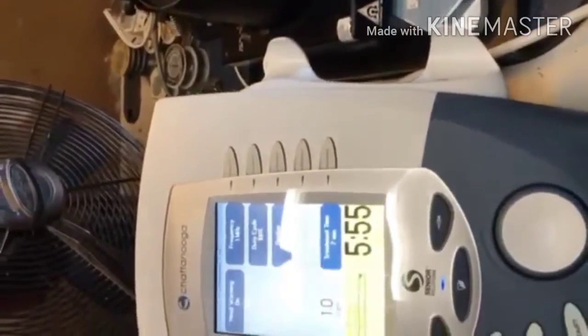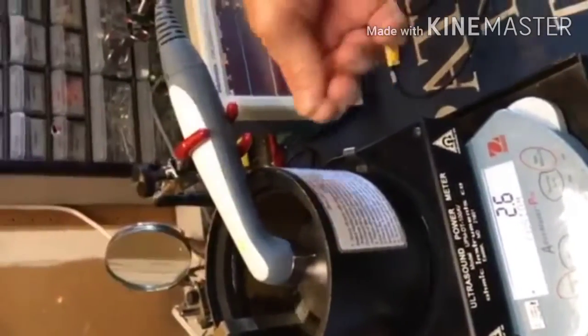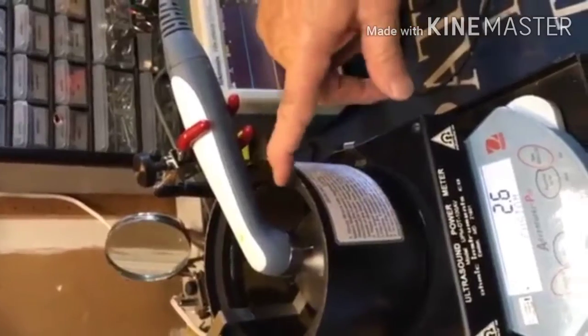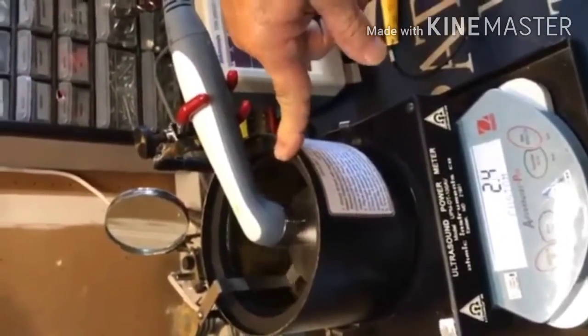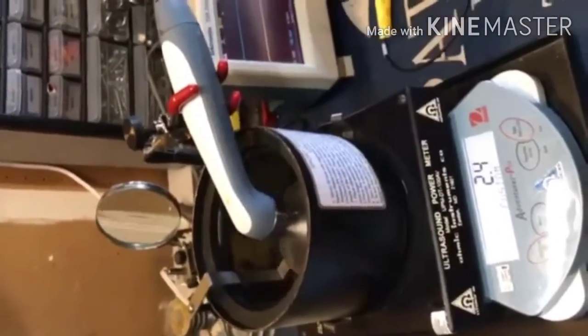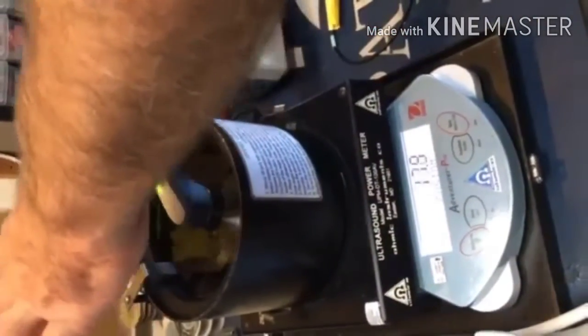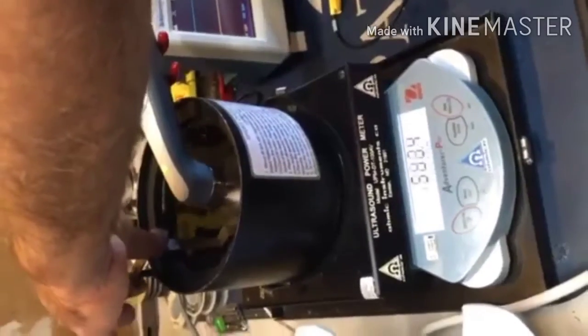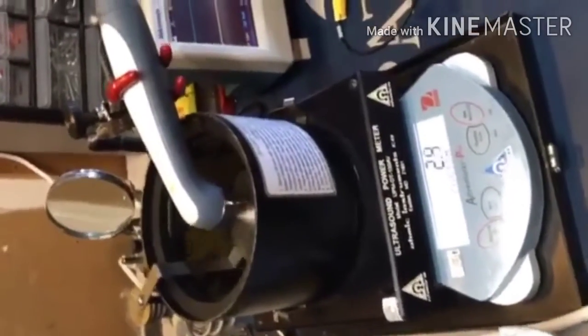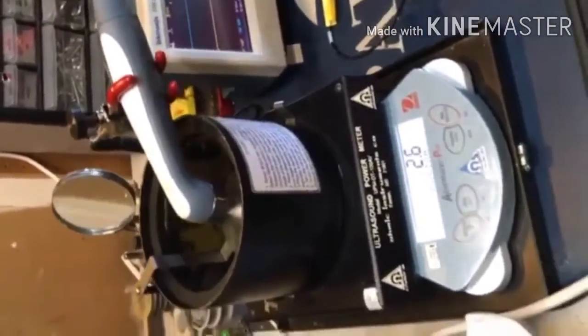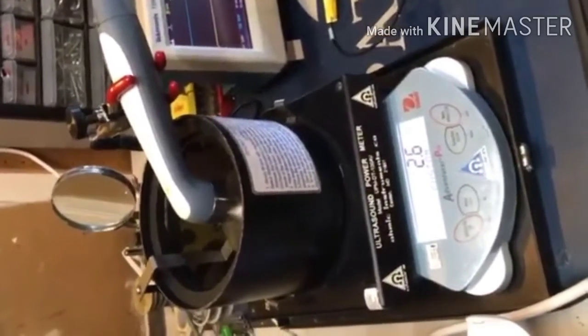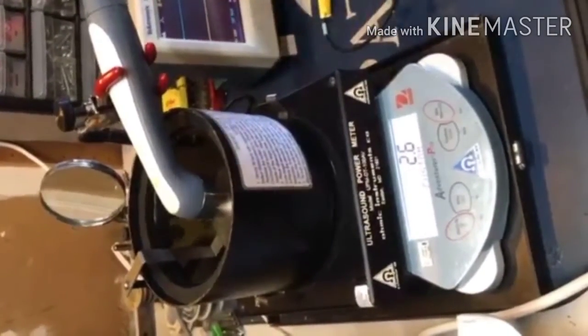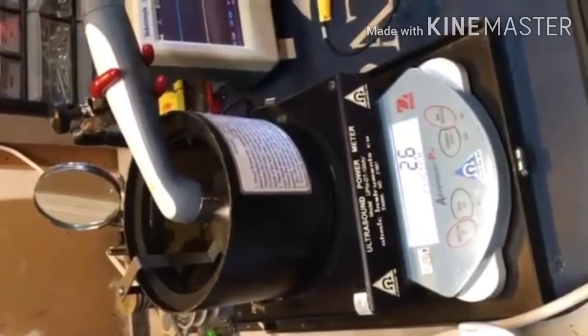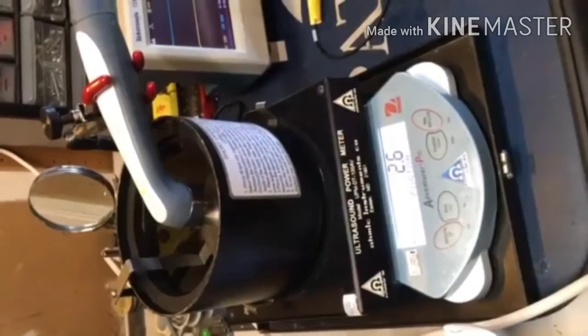The other thing is that a lot of times the sound head or the holder is pressing down on this, and you'll see if you press down on it, it's going to change. Sometimes that happens. Something happened, the cone's not in. There's stuff to do exactly before you freak out and say it doesn't work. You troubleshoot basically. If all that seems to be in place and none of those things are interfering, you've got a calibration issue.